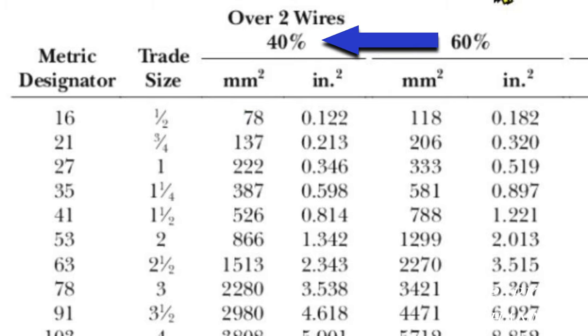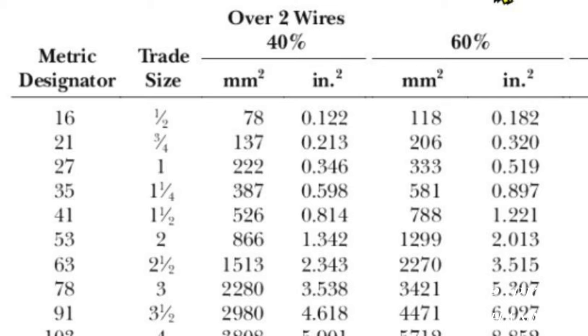And here's our trade size right here: half-inch. And it says over two wires, 40 percent. That means you're not to fill your conduit over 40 percent. And then you can use these numbers to do the math, but I'm going to show you what I think is an easier way to do it.